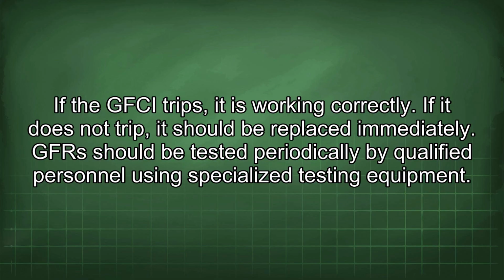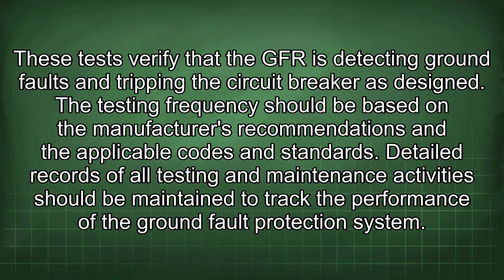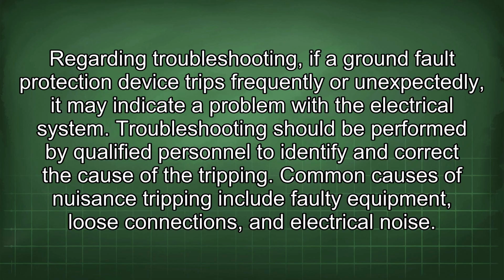GFR should be tested periodically by qualified personnel using specialized testing equipment. These tests verify that the GFR is detecting ground faults and tripping the circuit breaker as designed. The testing frequency should be based on the manufacturer's recommendations and the applicable codes and standards. Detailed records of all testing and maintenance activities should be maintained to track the performance of the ground fault protection system.